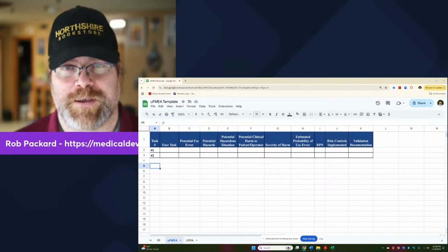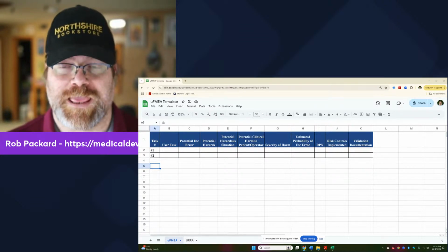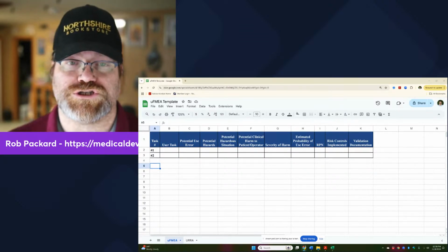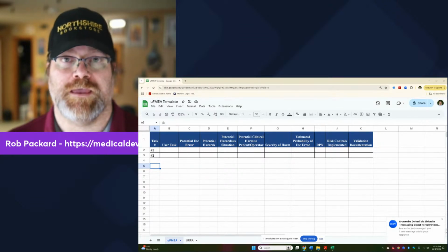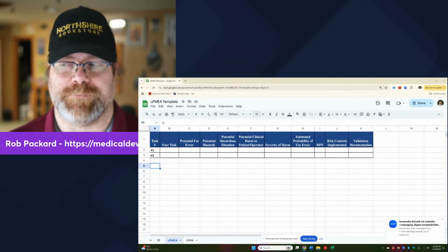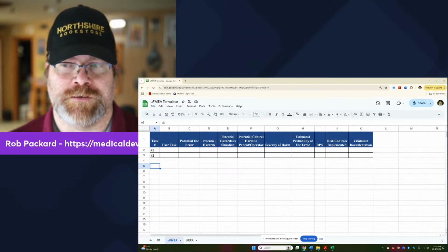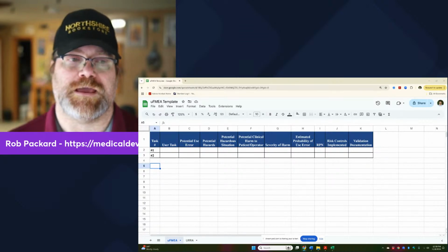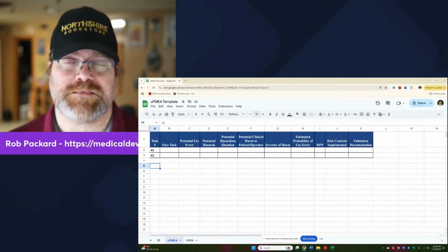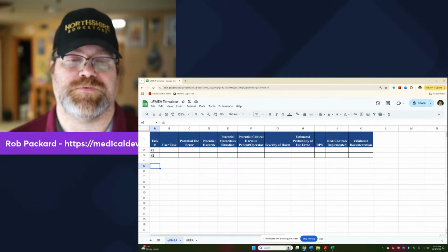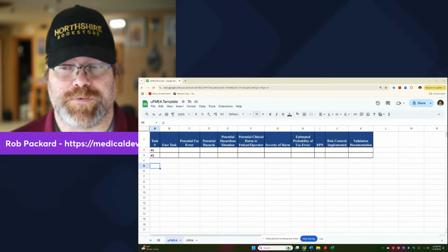And then we have specialist users. So an oral surgeon might use devices that are intended for doing oral surgery. A radiologist might use devices that are intended for analyzing or measuring radiology images or taking radiology images. So you have specialist users, professional healthcare users, and then we have laypersons. And you can even segment that further by looking at different demographics like age, education, language, lots of possible ways you can slice and dice the demographics of your user population, but you're required to define who that user population is.